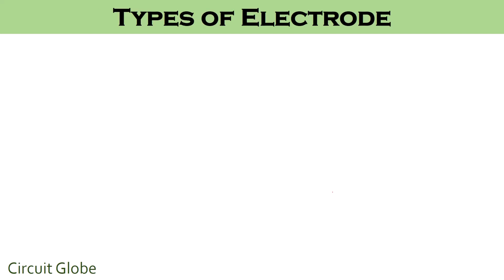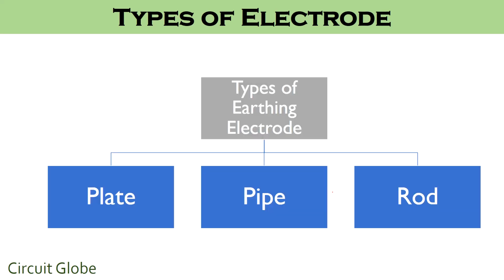We have already discussed that electrodes are crucial components of the earthing system. Let us now see how electrodes are classified. Guys, keep in mind that the way electrodes are classified is a similar way in which earthing is classified. So basically there are three types of earthing electrode: plate, pipe and rod. Guys, in plate earthing, a metallic plate of copper or galvanized iron is buried within the ground. Generally, copper plate is not used due to its high cost, so in most of the cases, galvanized iron plate is used. The second one is pipe earthing.